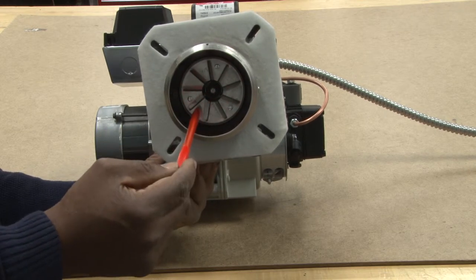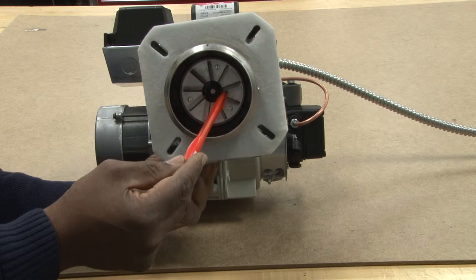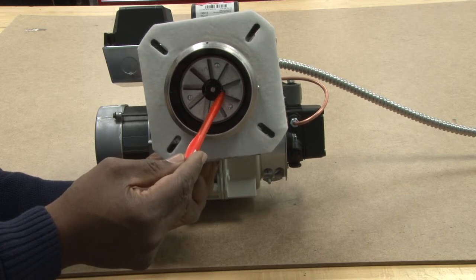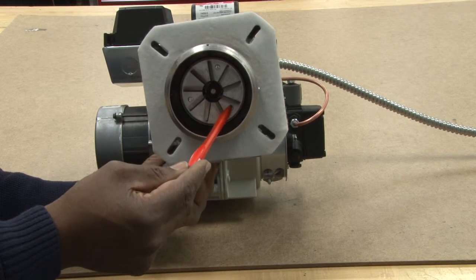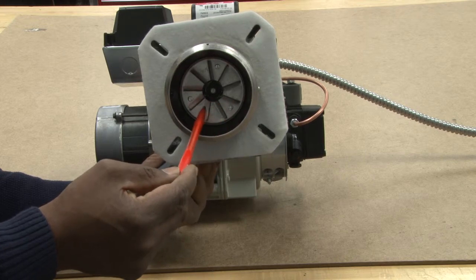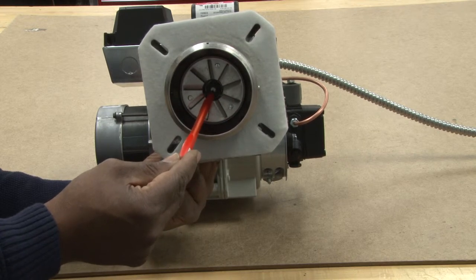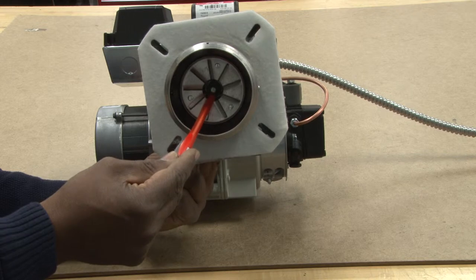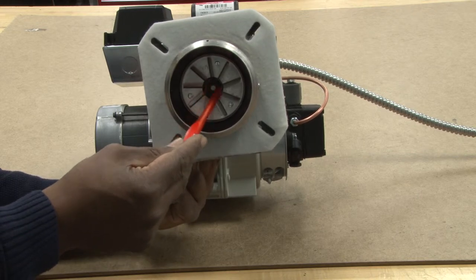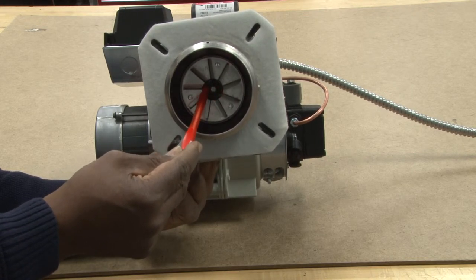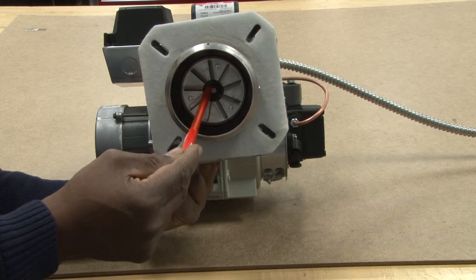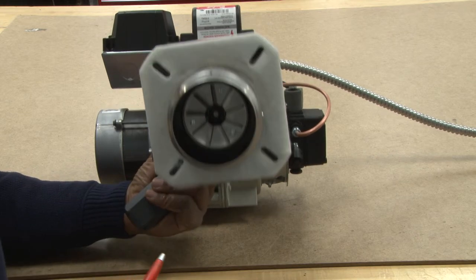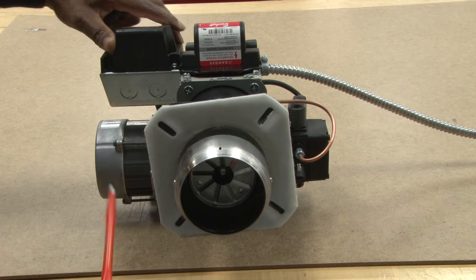There are many different types of flame patterns you may have. One may be a hollow cone or a solid cone, or it could be a combination of both of those together. In its very center is the nozzle, and the nozzle is mounted here, and just above the nozzle is where the electrodes are to ignite the oil from the burner pump.